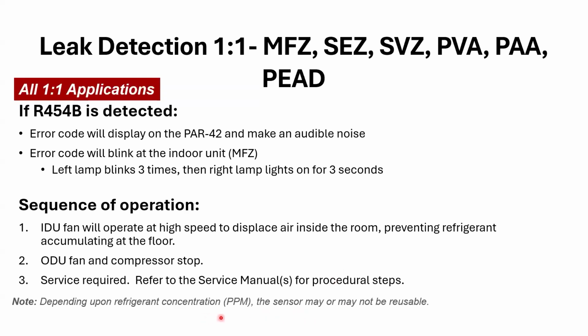Yeah, depending on, let's see, beeping noise. Yeah, the beeping noise, I see a note at the controller, 65 decibels is what that PAR 42 controller is going to beep. Sensor can fail. They kind of say this, if the sensor, it may or may not be reusable. So, I'd say this, if it does detect something and you take care of the problem and ventilate it and the sensor is working again and does still work, then I would probably just reuse the sensor. It depends on the concentration level, like it says.